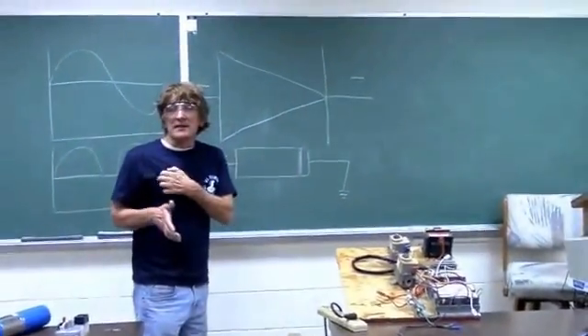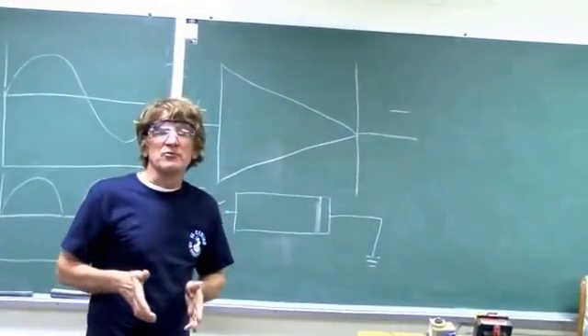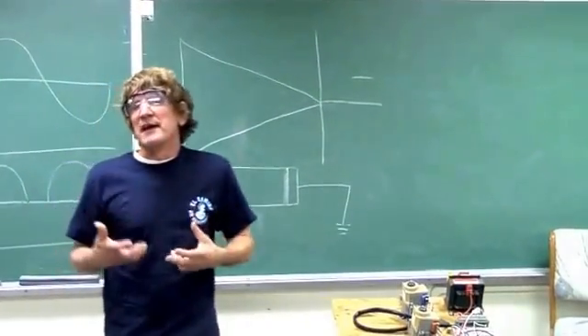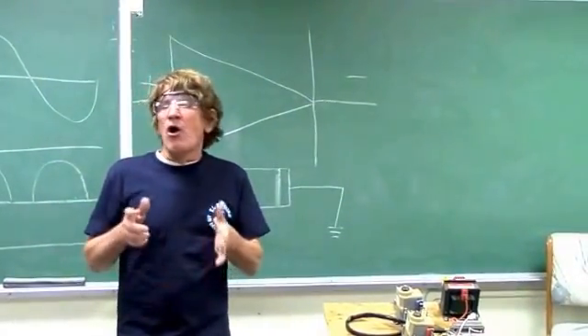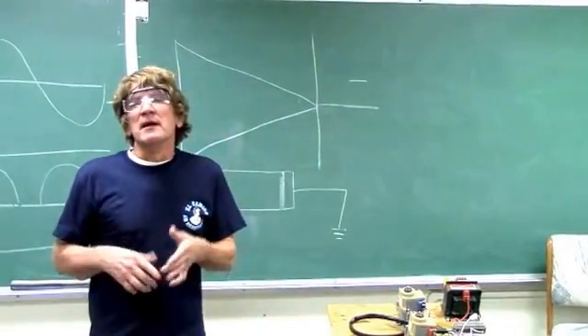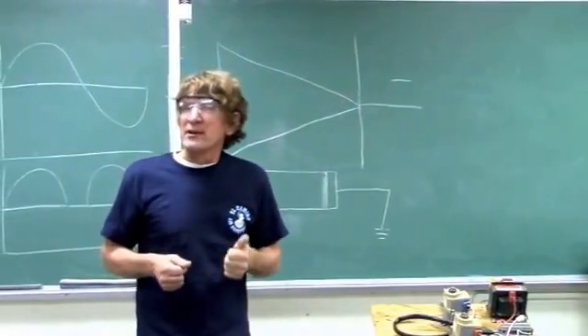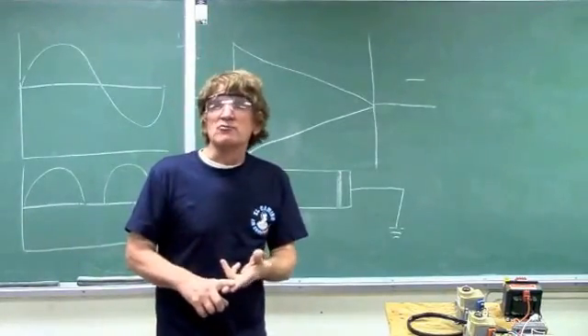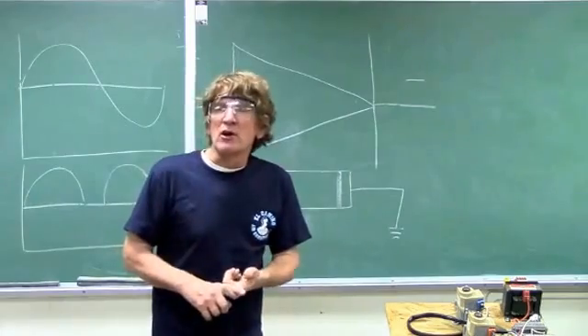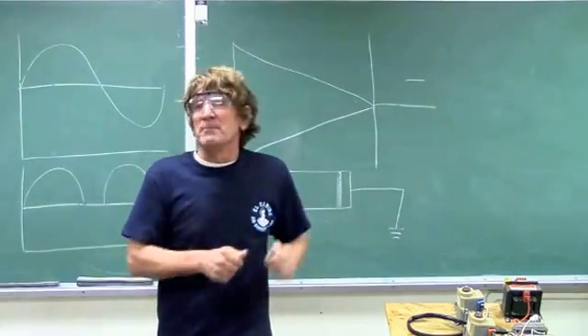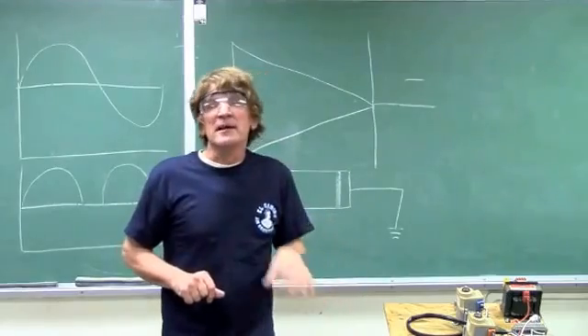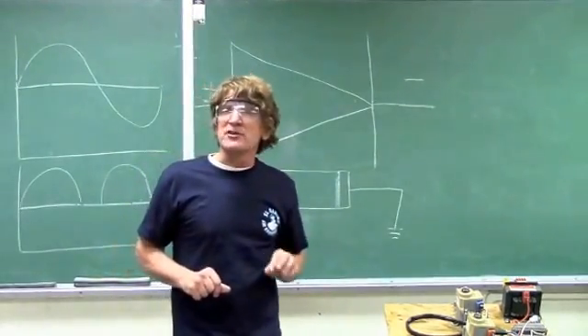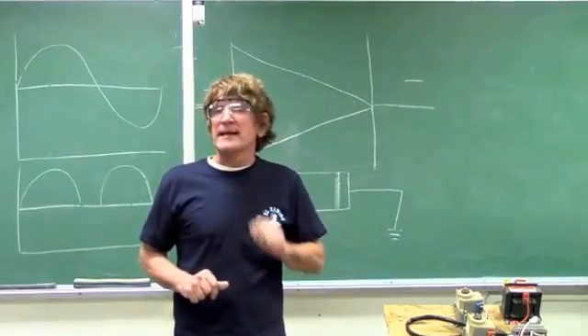I need to simulate this. Let's say I think I have a bad gas valve or a bad module. I need to simulate flame rectification because I've looked at my wiring diagram and verified all the other sensors are good. Into this module, I just have binaries telling me flame rollout is good, I've got power to the module, my high temp limits are closed. Assuming all that — or I've jumped that circuit out — now the module is powered and all the binary inputs are closed. The only thing I have to do is simulate that I actually have a flame so I can keep that gas valve on.